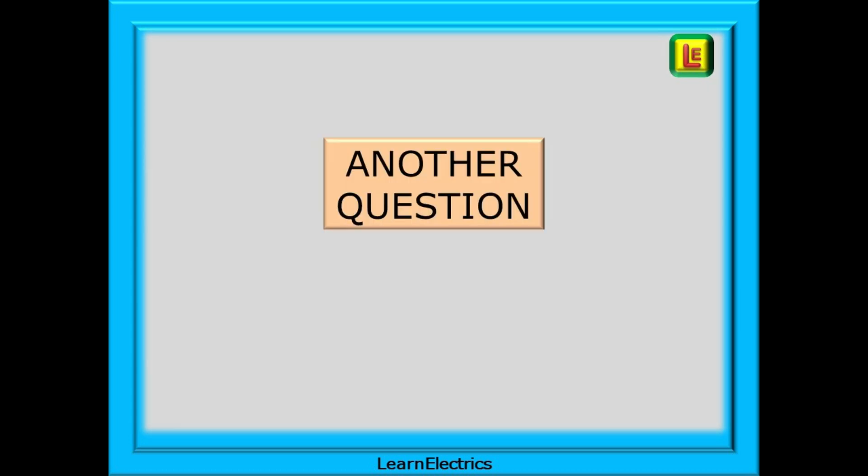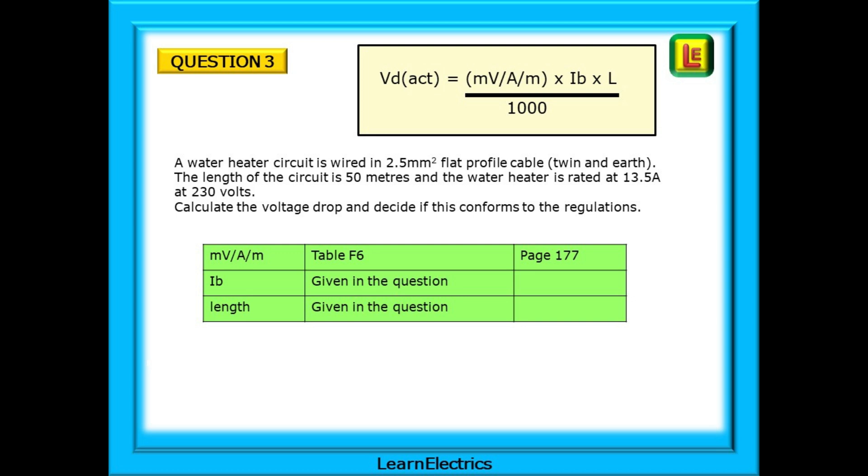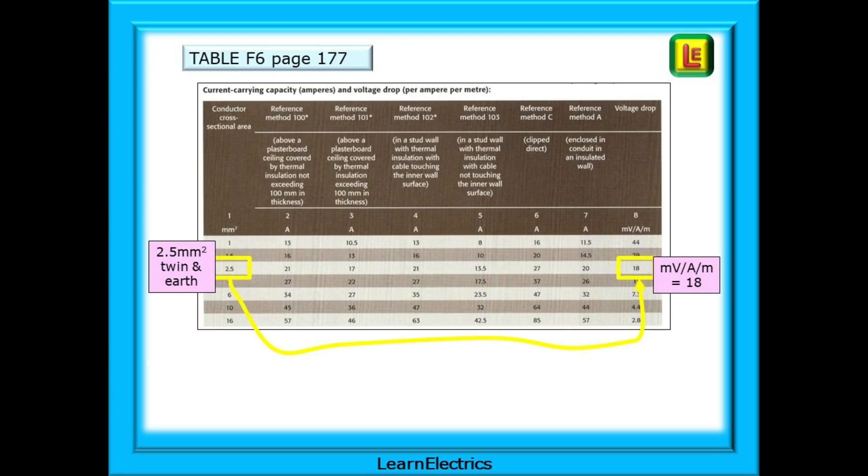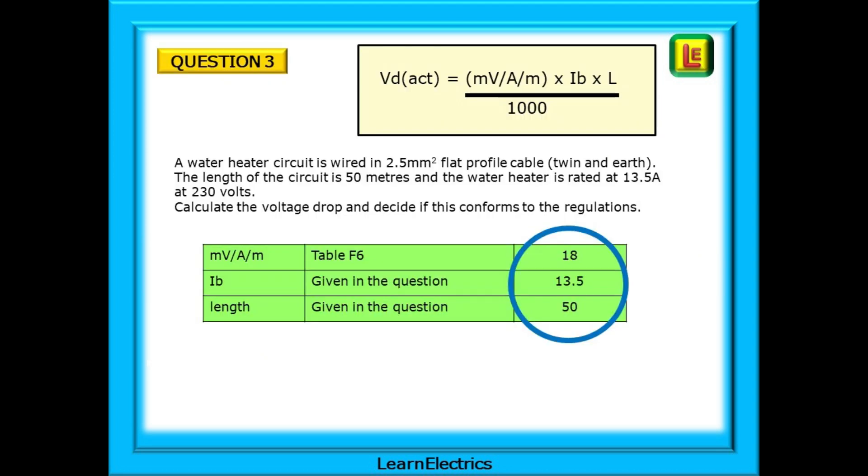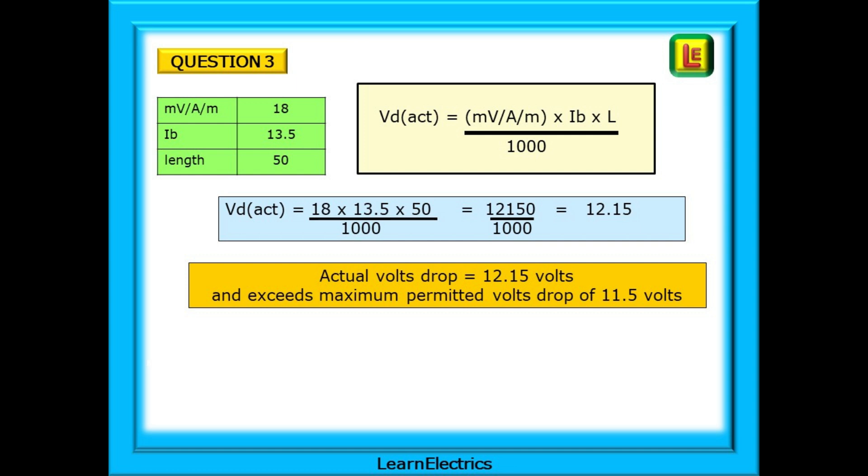Let's do another question. This time we have a water heater circuit that is wired in 2.5mm flat profile cable. The length of the circuit is 50 meters and the water heater is rated at 13.5 amps at 230 volts. We must calculate the voltage drop and decide if this conforms to the regulations. Off to page 177 again table F6 where we find the 2.5 twin-earth cable has an MVAM of 18. As before complete the list of what we need to know before making the calculation. Put the numbers into the calculator and we have an actual voltage drop of 12.15 volts clearly over the maximum voltage drop limit for this circuit.